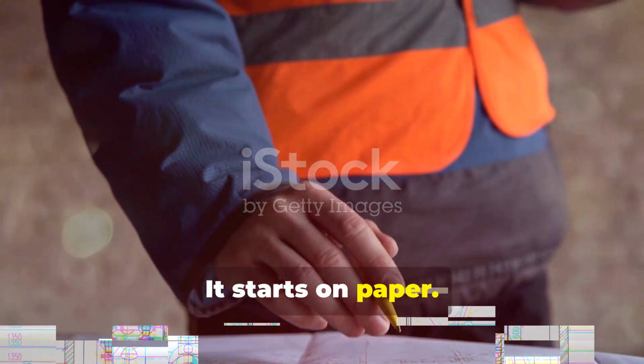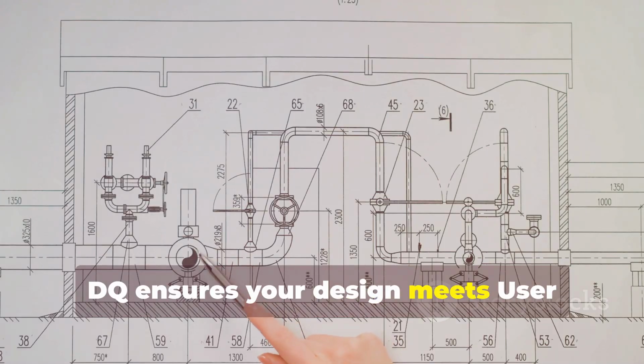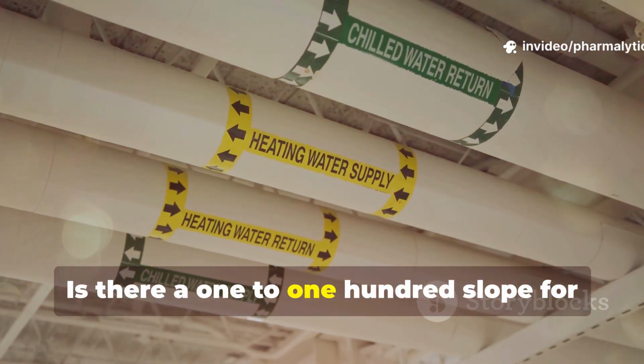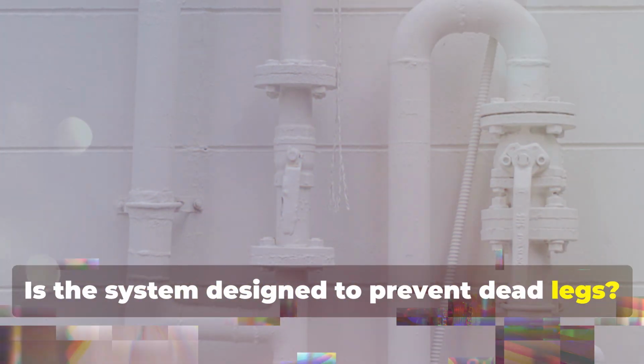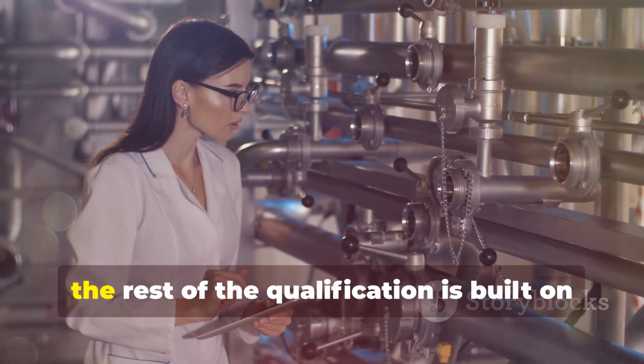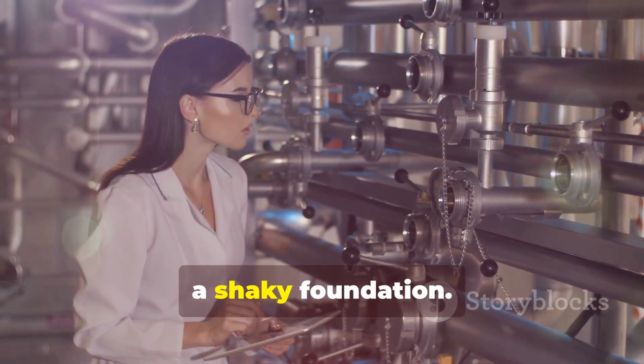It starts on paper. DQ ensures your design meets user requirement specifications. Are the pipes stainless steel 316L? Is there a 1:100 slope for complete drainage? Is the system designed to prevent dead legs? If it's not right in the DQ, the rest of the qualification is built on a shaky foundation.